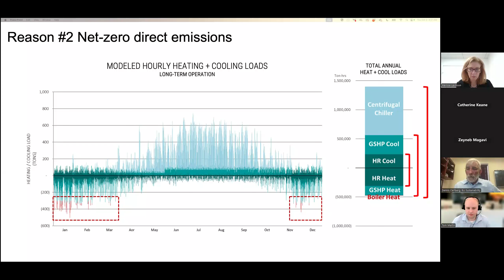Tom, do you want to add anything here? Sure. So this is a hybrid plant design where we have heat recovery chillers, ground source heat pumps, centrifugal chillers, and electric boilers. And I think the biggest challenge is getting the staging right to make sure that this system operates the way we need it to. So as Dennis said, first stage is building simultaneous, so that's the dark green. The second stage is ground source and heating mode or cooling mode. And then the final stage in heating is the electric boiler, and the final stage in cooling is the centrifugal chillers. Back to you, Dennis.